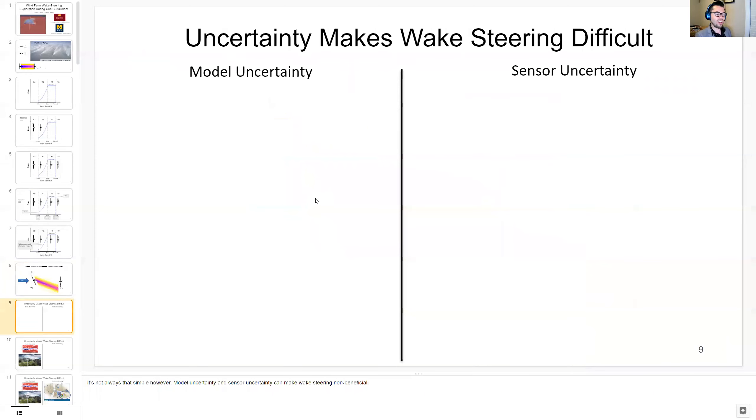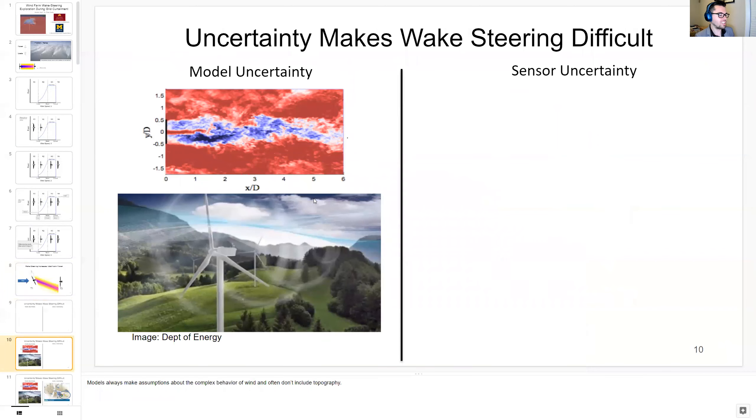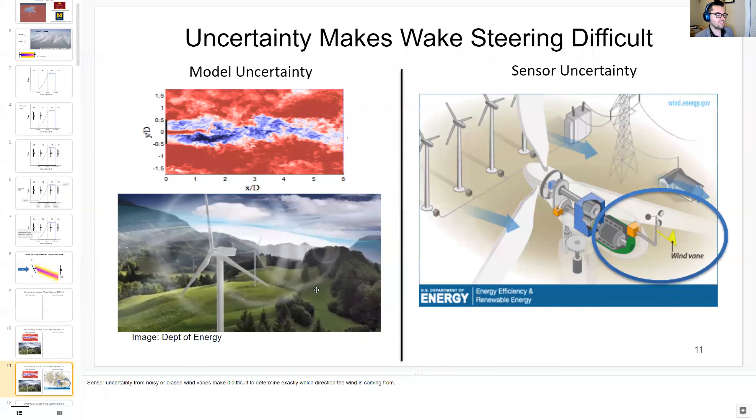It's not always that simple, however, because model uncertainty and sensor uncertainty make wake steering not as beneficial as it could be. Model uncertainty basically describes how models always make assumptions about the complex behavior of wind and often don't include topography in the wind farm that impact wakes. And sensor uncertainty is the noisy or biased wind vanes that make it difficult to determine exactly which direction the wind is coming from.